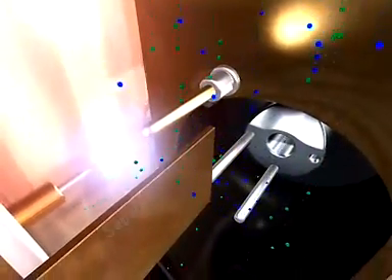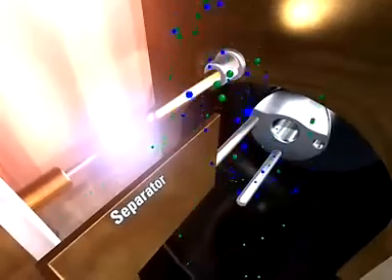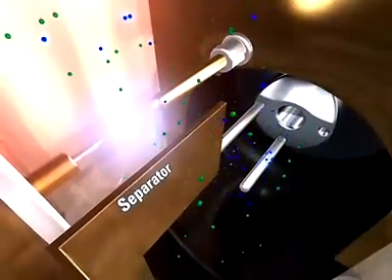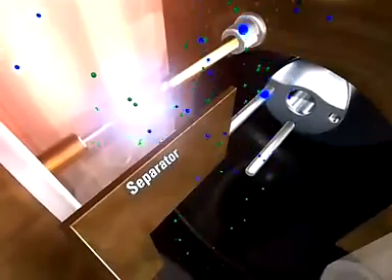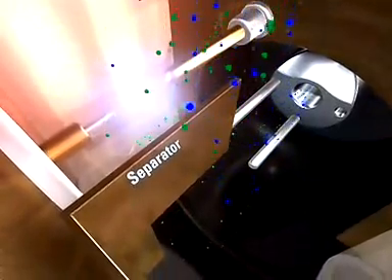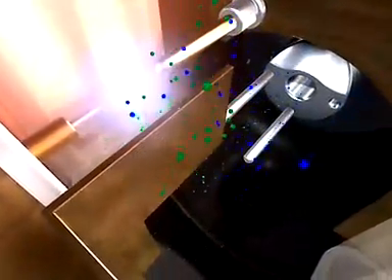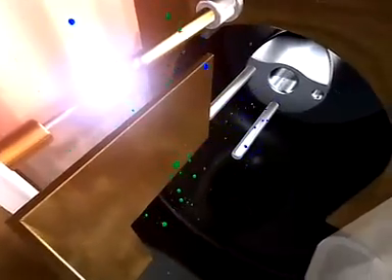Electrostatic fields and a physical barrier separate the electrospray ions from the region where atmospheric pressure chemical ionization takes place. Momentum carries the neutral solvent molecules and nebulizing gas out of the source through the drain hose.